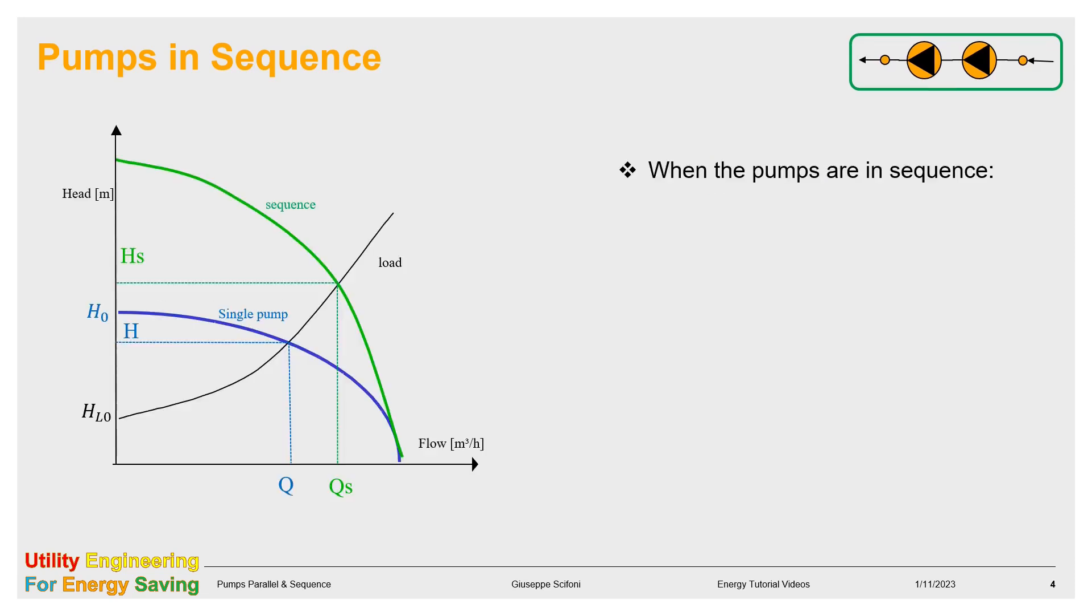When the pumps are in sequence, the corresponding heads are added, as we have seen. So, the curve of the single pump, the blue one, becomes the one displayed in green. The curve of the load, the black one, does not change instead. The working point moves along the load curve to match the green one. Actually, both head and flow changes, but if the pumps are correctly chosen, H increases more than Q.